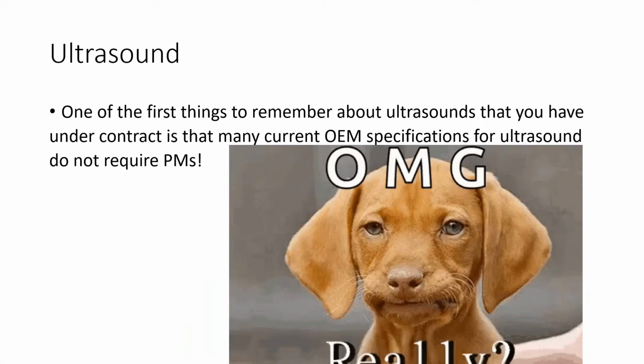Okay, ultrasound. One of the biggest things to remember, and I know not everybody has a background with imaging, is that many current OEM specifications for ultrasound do not require PMs. If it's under contract with the OEM, you're not getting a PM. They literally changed it so they wouldn't have to do that.